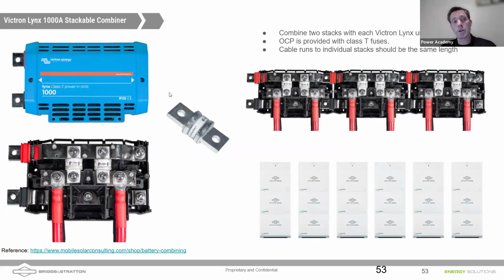Here's a nice way to combine them. We often talk about the Midnight 1000 amp combiner because that's been kind of the long gold standard for battery bank combiners, the 1000 and 2000 amp Midnight combiners. But Victron, just a couple of months ago, came out with this Class T power in. And this is 4/0 sized cabling, which you can do individual fuses on. So the negative cables are on the bottom of this. There's some tabs that flip up. I'm actually putting together a guide on using these right now, and it's very well made.